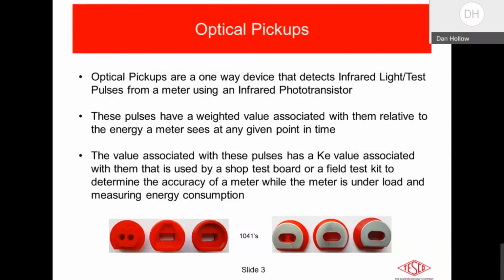They have a known associated weight with them, and then it determines the energy consumption for a test like a full load test or a light load test or a full load power factor test. And while the meter is undergoing these test sequences, the meter is putting out these infrared pulses, and those pulses are being counted by the piece of test equipment, whether that be shop or field test equipment.